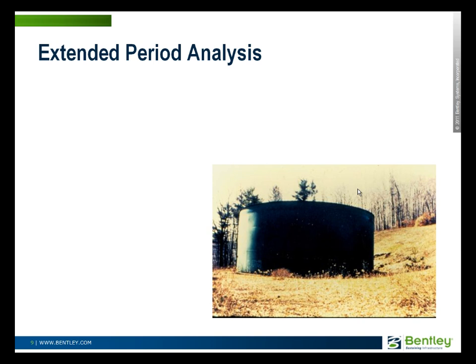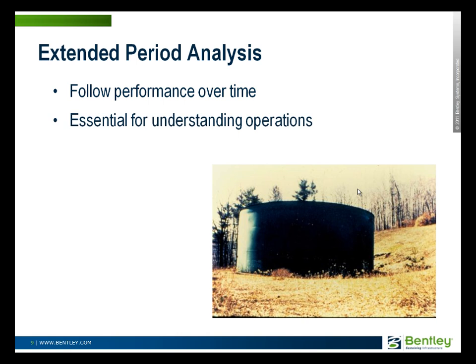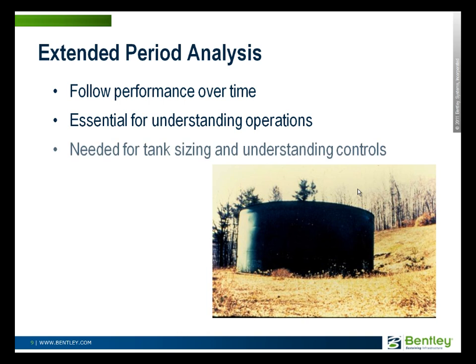Most of those runs would be done in steady state, but extended period analysis gives you a lot of extra information in that it follows the performance of the distribution system over time. It has many uses in understanding operations, because operations of water systems are not static — they continuously change over time. Extended period simulation models are very important for understanding distribution system operation, for tank sizing to determine if you have enough volume of water, and for understanding control settings: at what tank levels or other conditions would you turn pumps on or off, or change the status of valves.